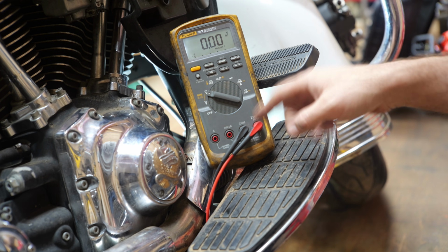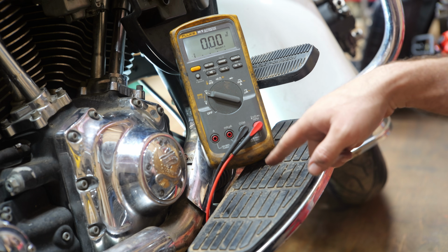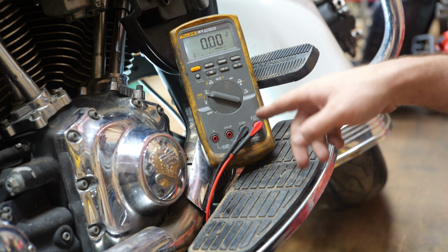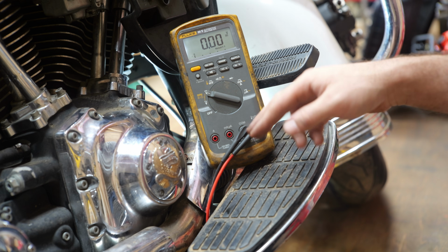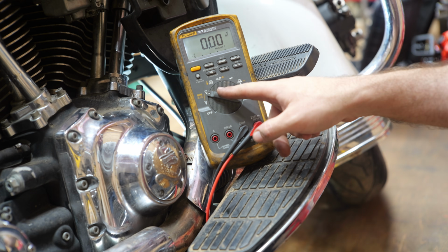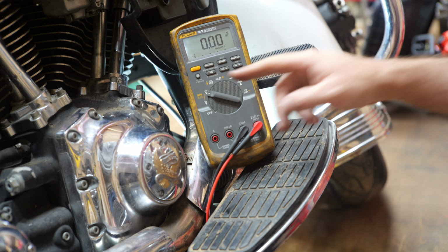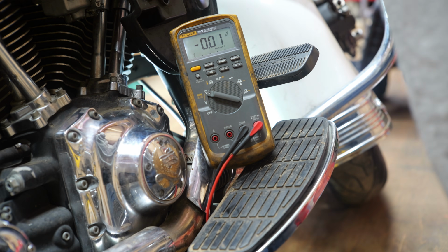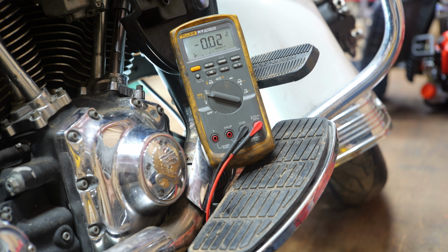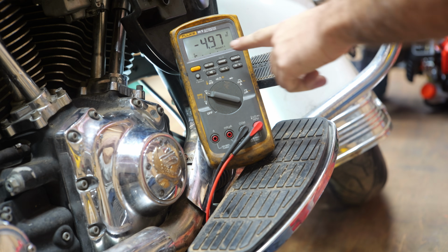Okay, so we are pinned in with the back probe spoons down there on our cam position sensor, across the green and white, and the black and white is where our two spoons are. We're back on DC volts, and we're gonna turn the main switch power on, key switch power on, and we've got 4.97 volts—I've got the leads swapped, but it doesn't matter. The spec here is with the ignition on and the engine off, we should have 0 to 5 volts DC power, which we do.